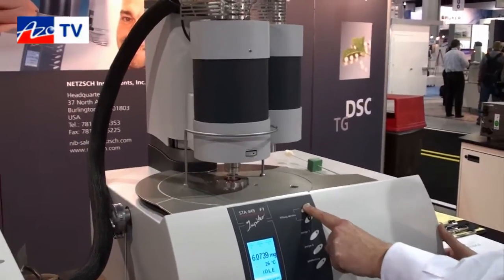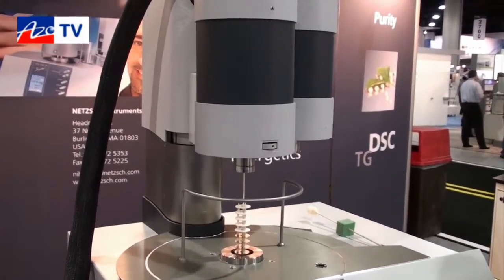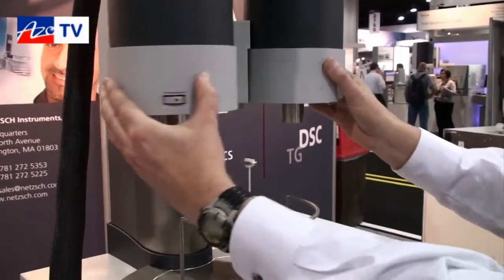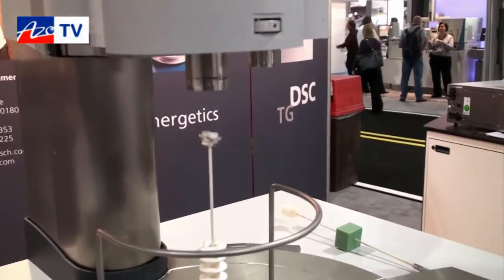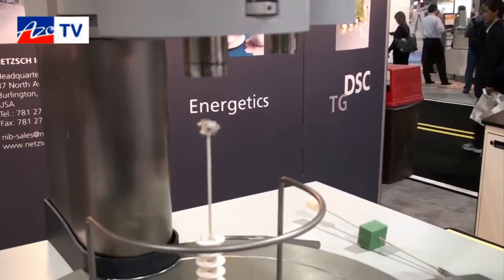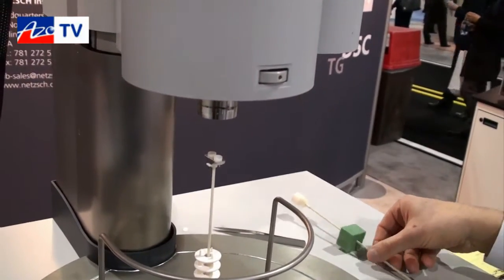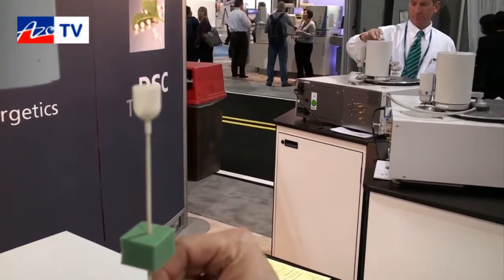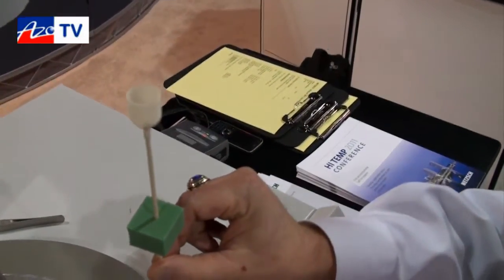You've got a furnace that sits on top of the sample. The system has the capability to add up to two furnaces, and you can change back and forth between furnaces very easily. Different sensors allow you to measure different properties. This is a DSC sensor mounted into the microbalance that gives you simultaneous DSC and TGA. What's really unique about the NETZSCH instruments is you also have the capability to measure large or jumbo sample TGA measurements — that's quite powerful.